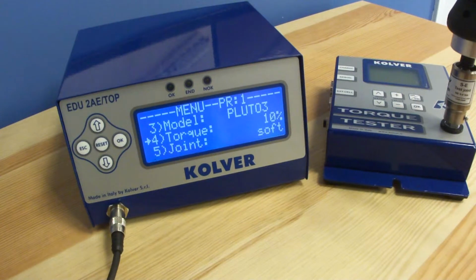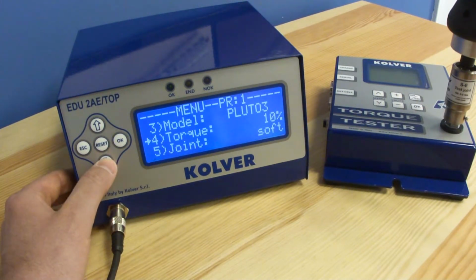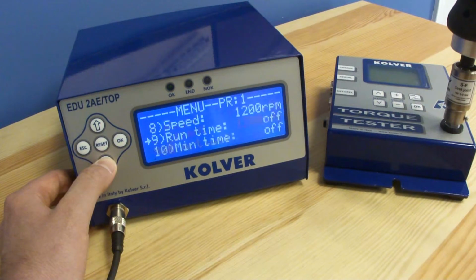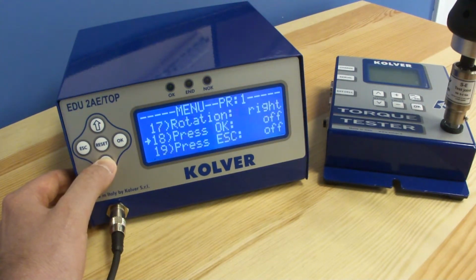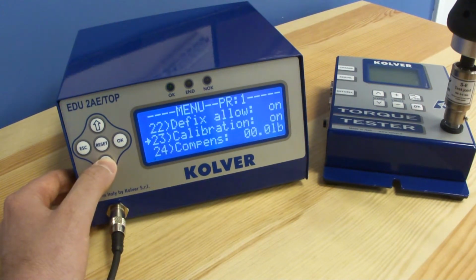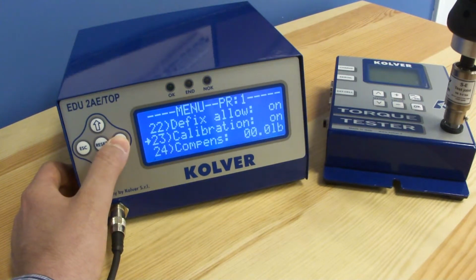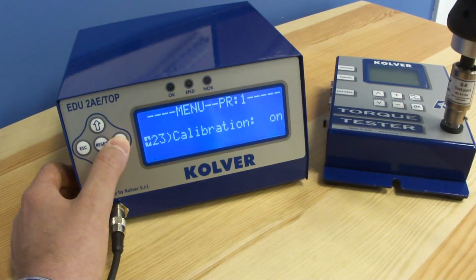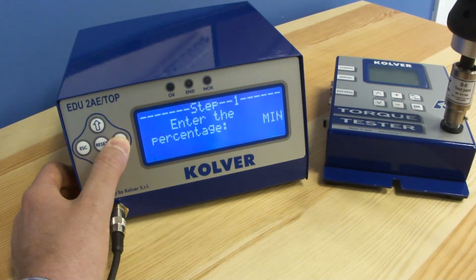In this case, I did 20 rundowns and validated that the 10% torque representation is equal to an average mean of 6.8 inch-pounds on our calibrated torque tester. Once we've done this process, we're able to go to the calibration menu and complete the calibration process. By clicking OK, we now enter the calibration menu.